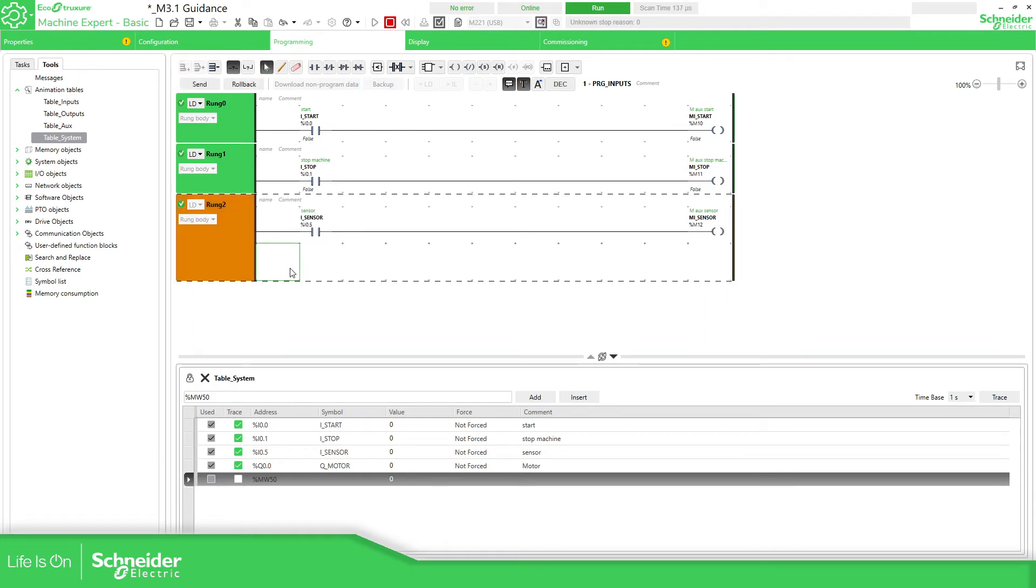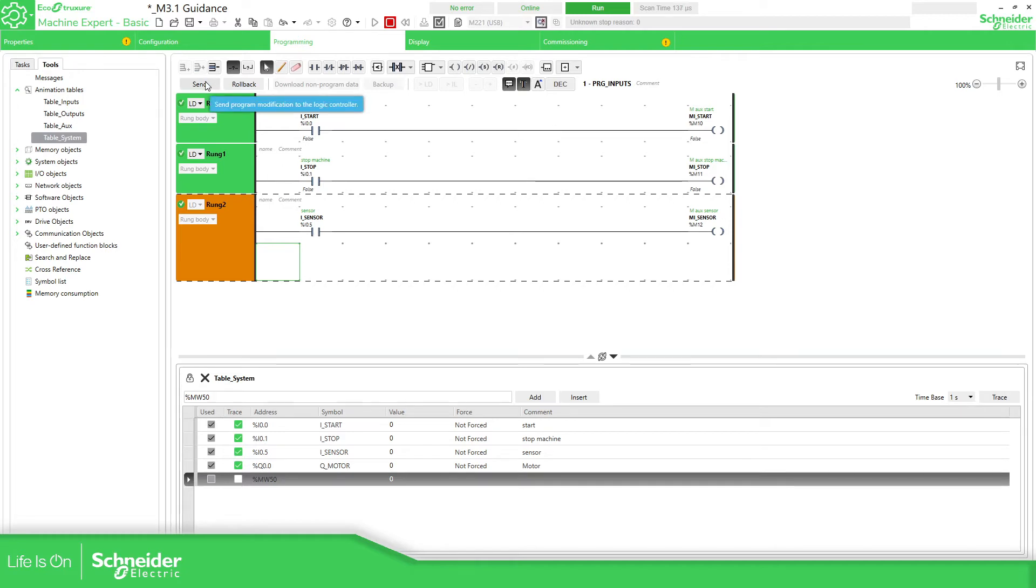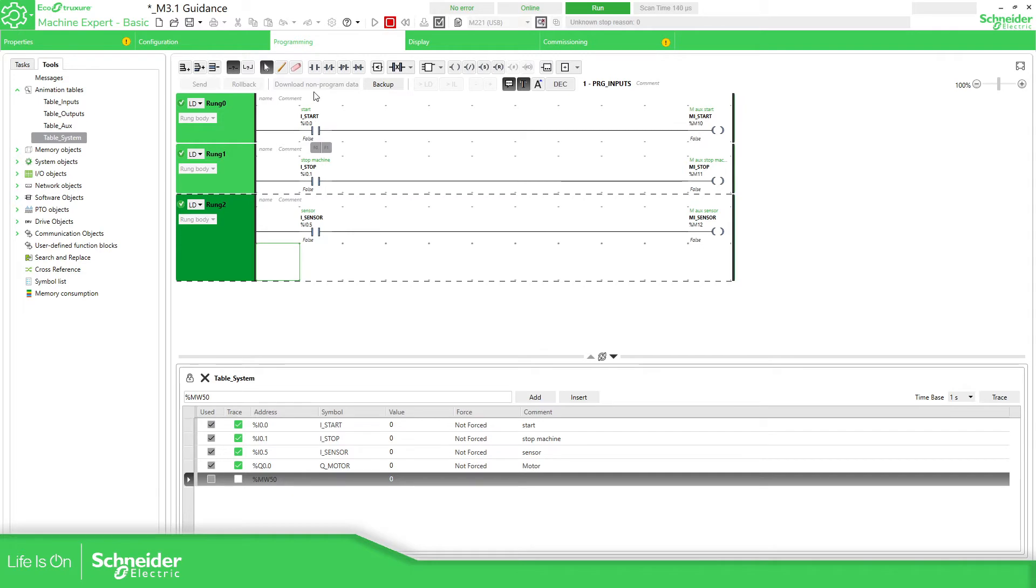Change. And what I need to do is to press the command send. So we can only send per one rung. We cannot make modification in all the rungs. We just need to press on one, make the modification, and then send. So send, and there we go. And online again, everything is working fine.